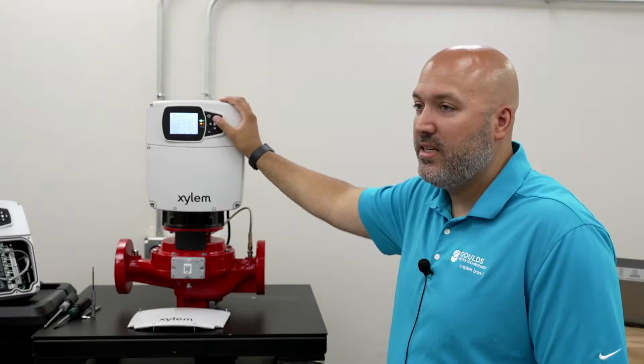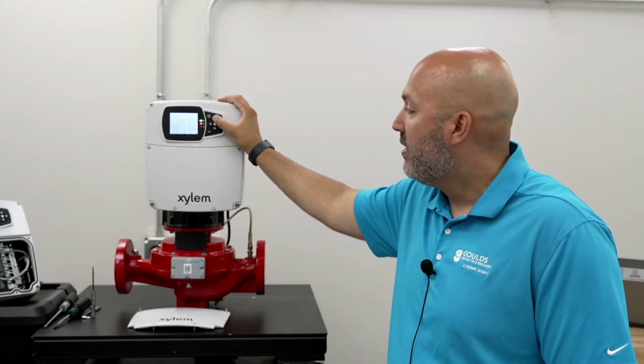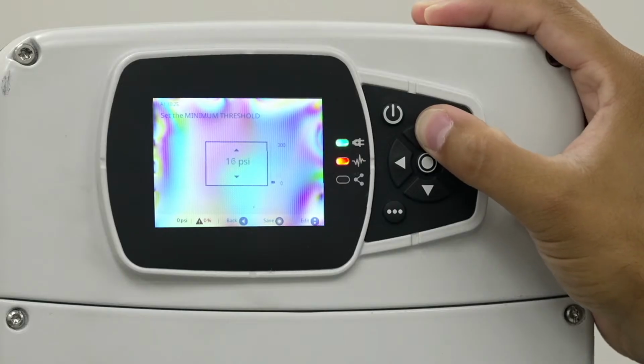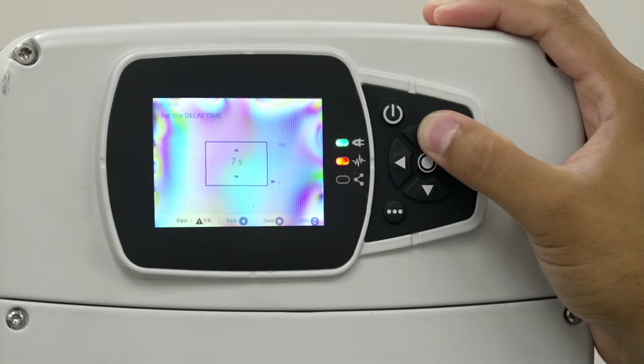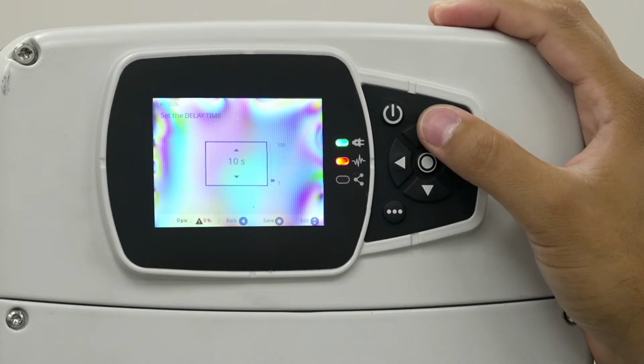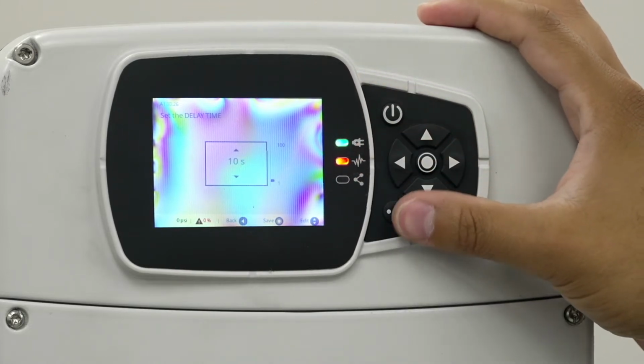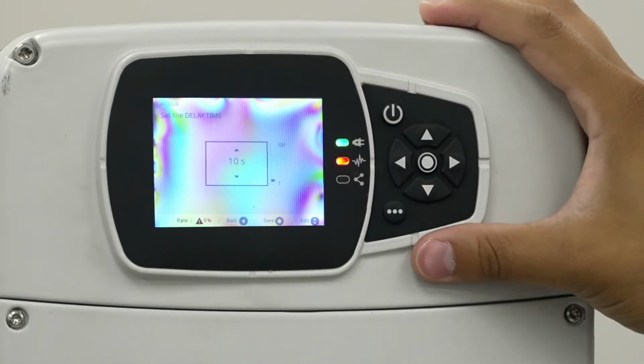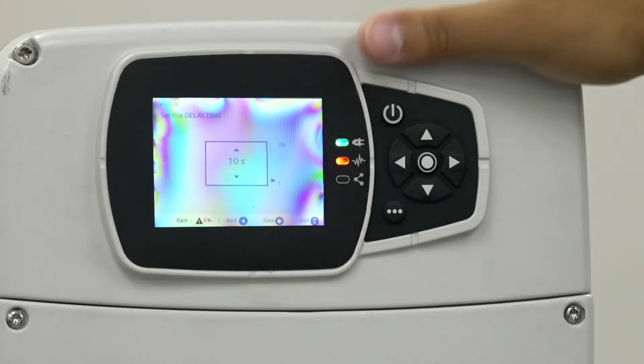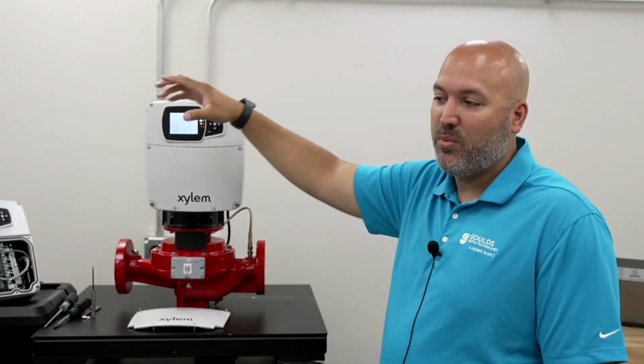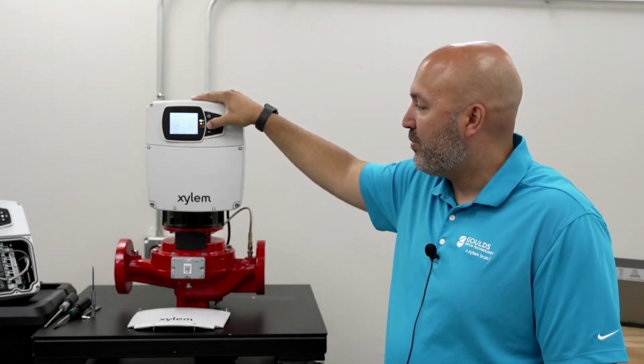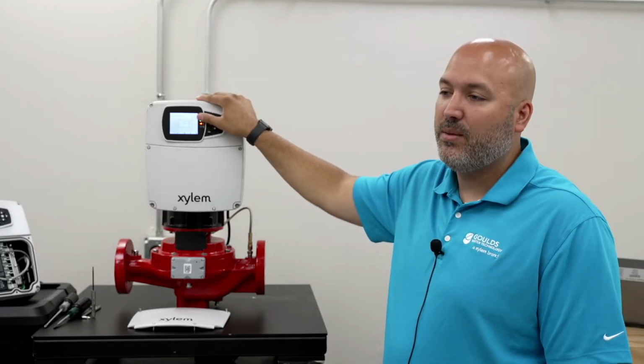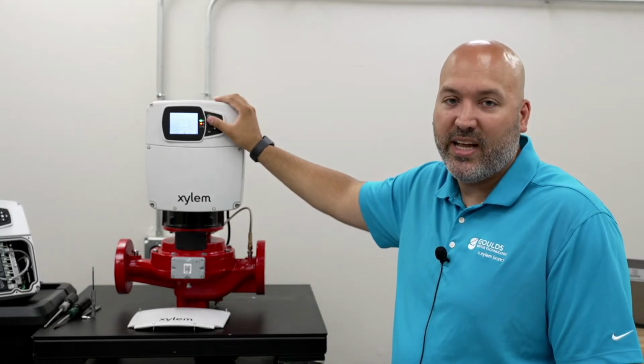Minimum threshold, this is essentially, I'll call it a minimum or a broken pipe feature. So you're going to set a PSI that you want this to go to. Let's just say 30 PSI, for example. And then there's going to be a delay time. So basically it's telling you how long it should take to get to that 30 PSI. So if I set this to 10 seconds, it's telling the unit, if I don't achieve that 30 PSI you set in 10 seconds, I'm going to kick off because I'm assuming something's wrong. My example is that broken pipe. So let's say there's a broken pipe on the discharge. If you don't have that minimum threshold set, the pump is just going to continue to pump, try to ramp up and hit that 100 PSI, and it's never going to because there's a pipe broken and we're flooding a facility. This is just going to capture that. It's saying, oh no, I'm not getting to where I need to be in a set amount of time. Something must be wrong. I'm going to turn off to prevent some sort of disaster like that.